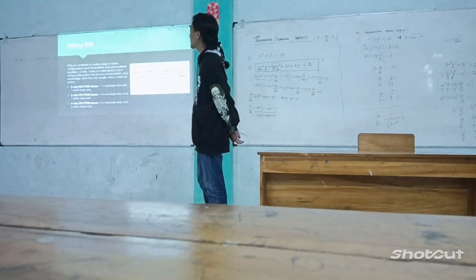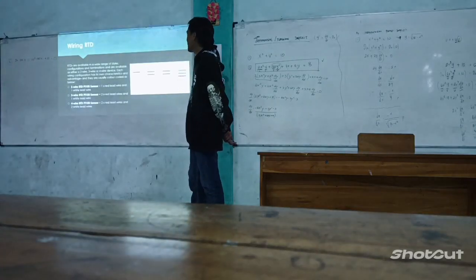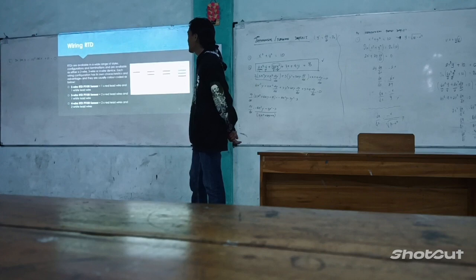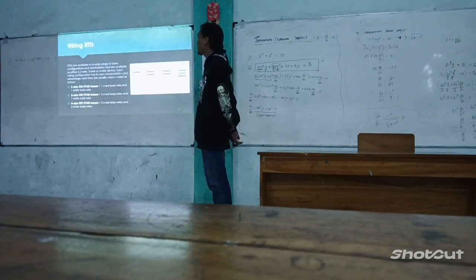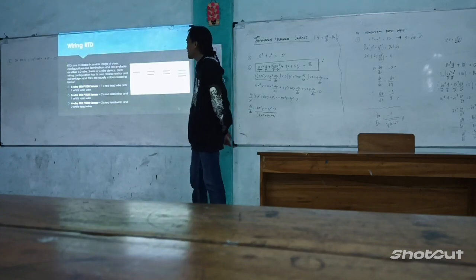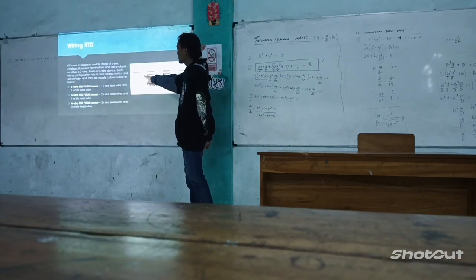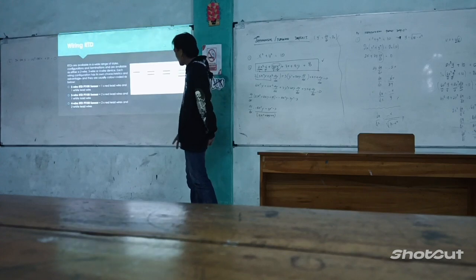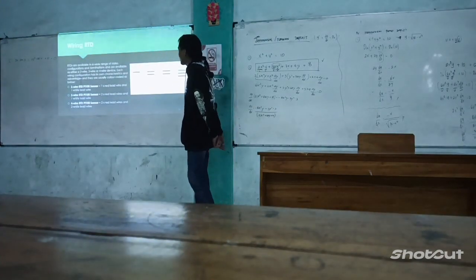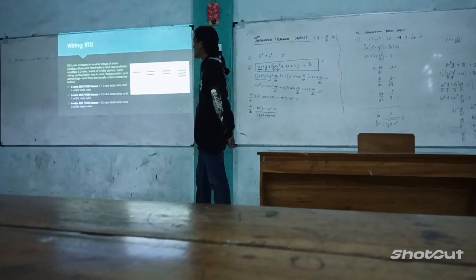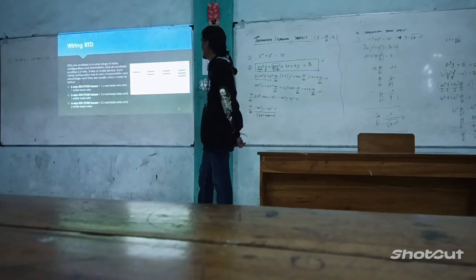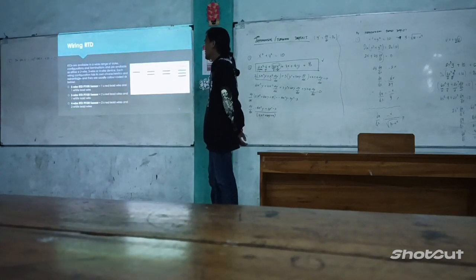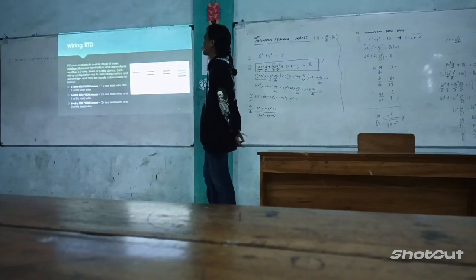Wiring RTD. RTDs are available in a wide range of styles, configurations, and terminations, and are available as two-wire, three-wire, or four-wire devices. Each wiring configuration has its own characteristics and advantages, and they are usually colored as below. First, we have the two-wire RTD PT100 sensor. It has one red lead wire and one white lead wire. The three-wire RTD PT100 has two red lead wires and one white lead wire, and the last is the four-wire PT100. It has two red lead wires and two white lead wires.